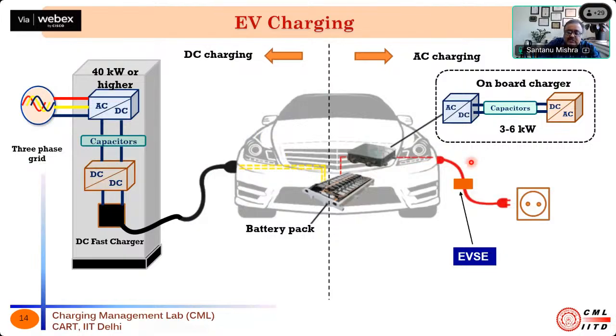But mostly if you use a 15 ampere plug, naturally you cannot charge the vehicle at 7 kilowatts. So if you use a 15 ampere plug, your charging power will be 15 amperes times 230, assuming the power factor is unity, which it actually is. That gives a number somewhere around 3 kilowatts.